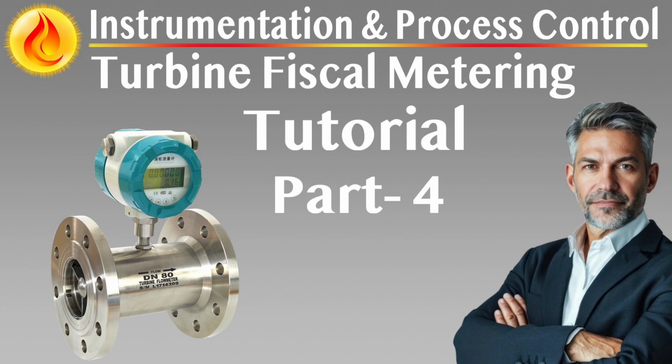All calculated variables, gross volume, mass flow, corrected volume, and running totals must be locally displayed and stored. Displays must be clear, unambiguous, and of sufficient resolution to verify compliance with calculation precision requirements. Additionally, the stream microcomputer must permanently display the accumulated mass quantity with enough digit capacity to record at least 3 months of maximum flow without rollover. Daily totals must also be recorded, resettable only at specified intervals.